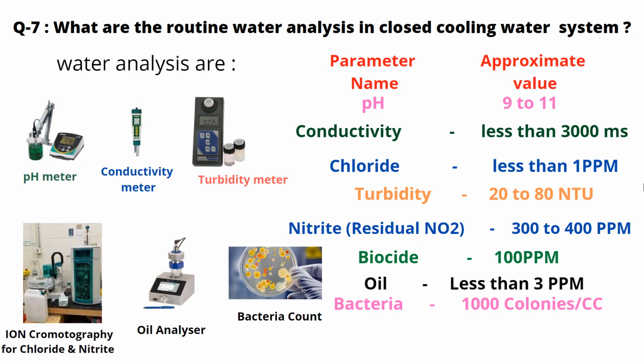What are the routine water analyses in the closed cooling water system? Water analysis parameters and approximate values: pH 9 to 11, conductivity less than 3000 millisiemens, chloride less than 1 ppm, turbidity 20 to 80 NTU, nitrite residual NO2 300 to 400 ppm, biocide 100 ppm, oil less than 3 ppm, bacteria 1000 colonies per cc.